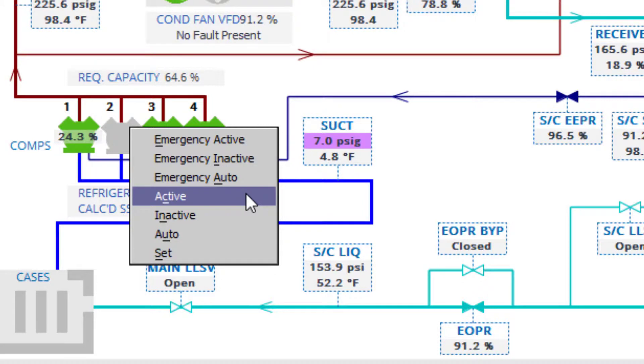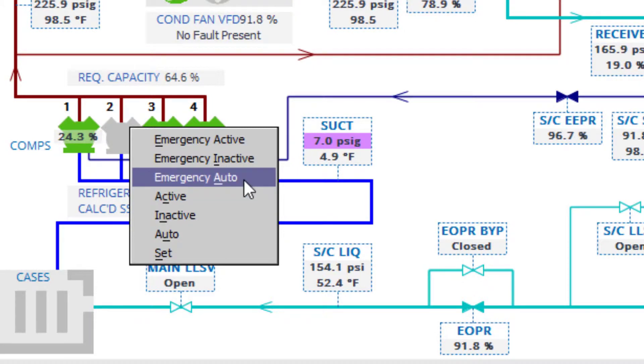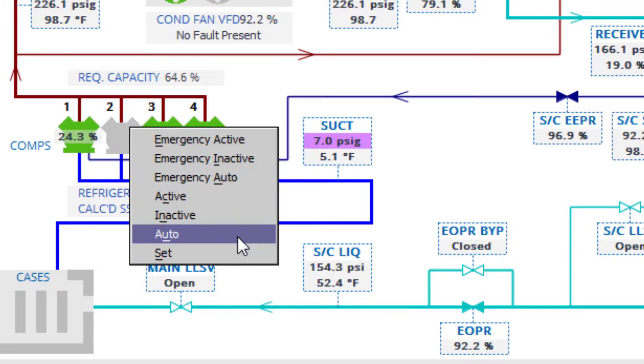Because of this, to disengage an emergency override, it must be returned to emergency auto state rather than just selecting auto, which would only clear a normal override command.